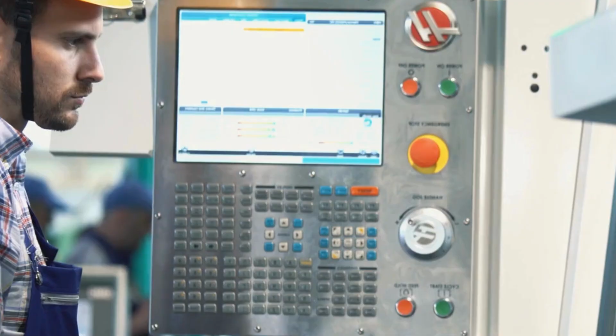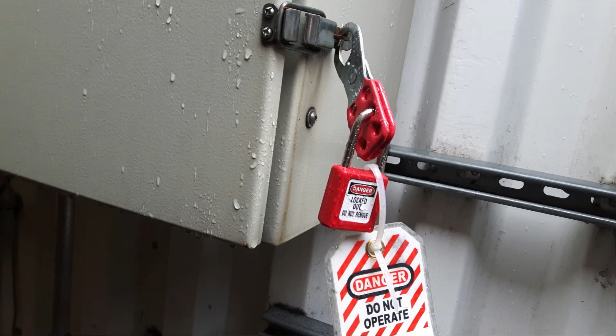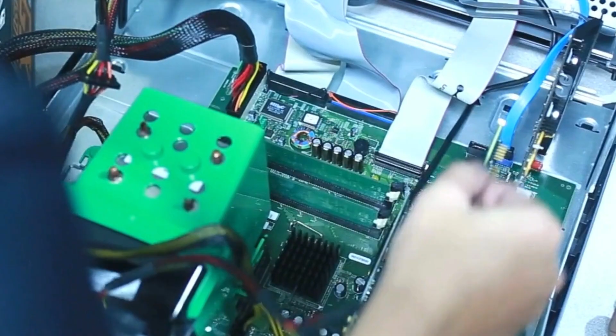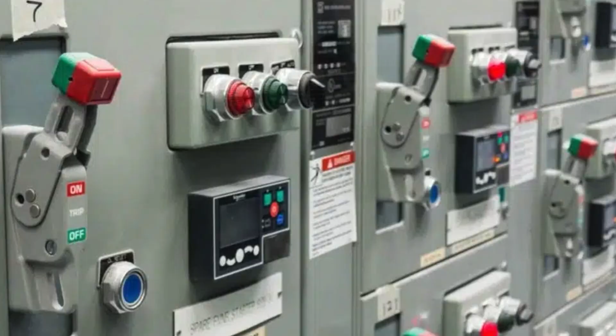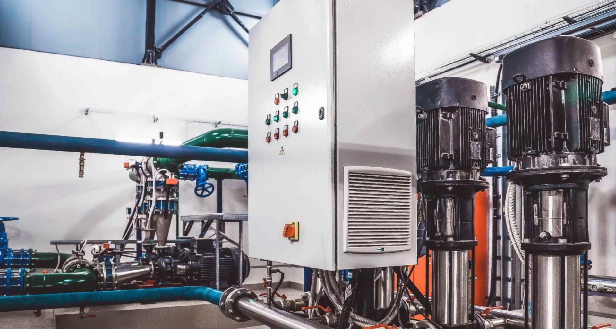Here are some suggestions when performing your investigation. For potential power issues, ensure whatever you are checking has been locked out and tagged out. Check the power supply and electrical connections to ensure all cables and connections are secure. Go to the MCC, Motor Control Center room, and see if the VFD, variable frequency drive, or motor has tripped.